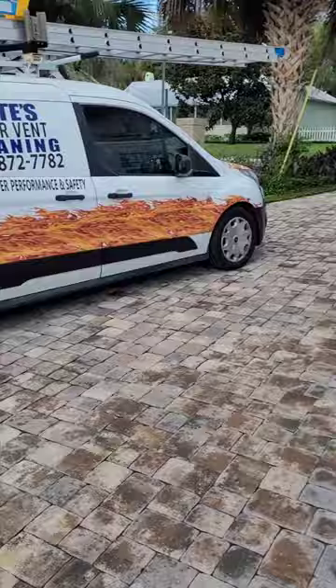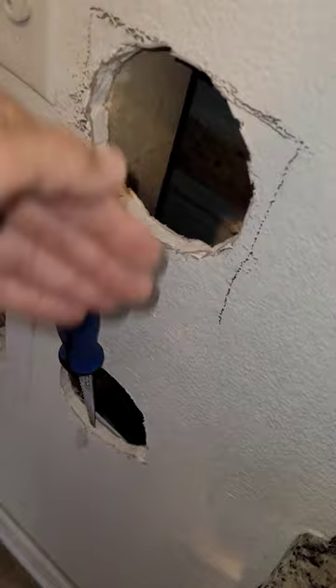This is the foil that we just took out. I'll show you where we just took it out from. The foil was being run from the dryer down into this hole. This hole was already made by the installers, and it was basically running four feet to the ground and then discharging one foot just underneath the house. I'll show you a video of that here in a minute.